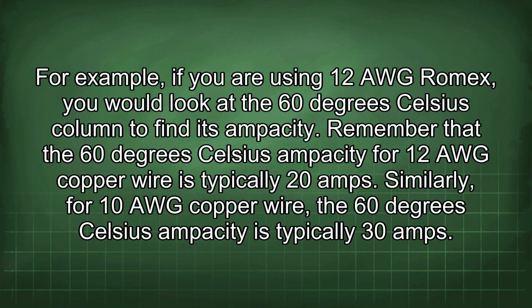For example, if you are using 12 AWG Romex, you would look at the 60 degrees Celsius column to find its ampacity. Remember that the 60 degrees Celsius ampacity for 12 AWG copper wire is typically 20 amps. Similarly, for 10 AWG copper wire, the 60 degrees Celsius ampacity is typically 30 amps.